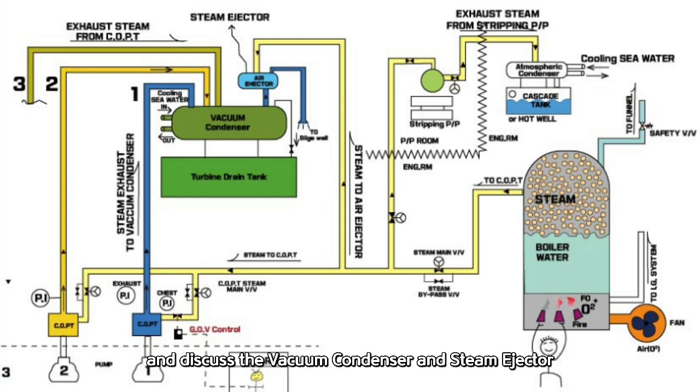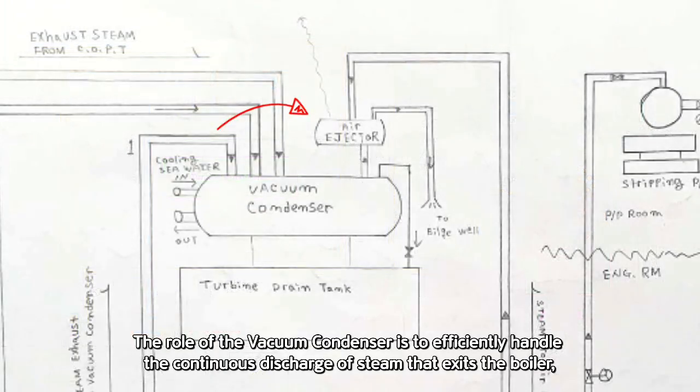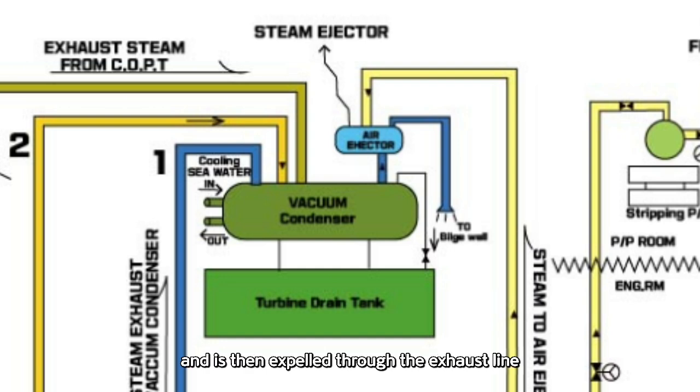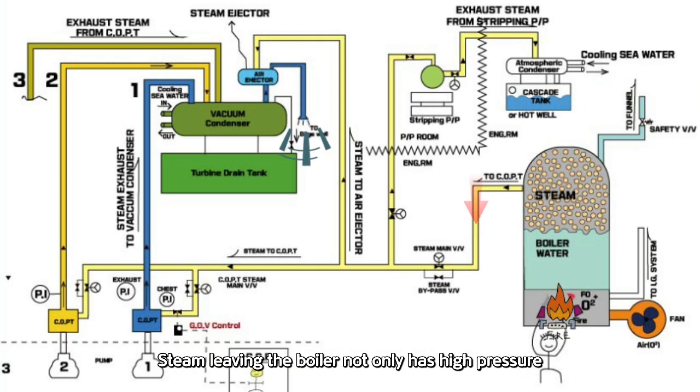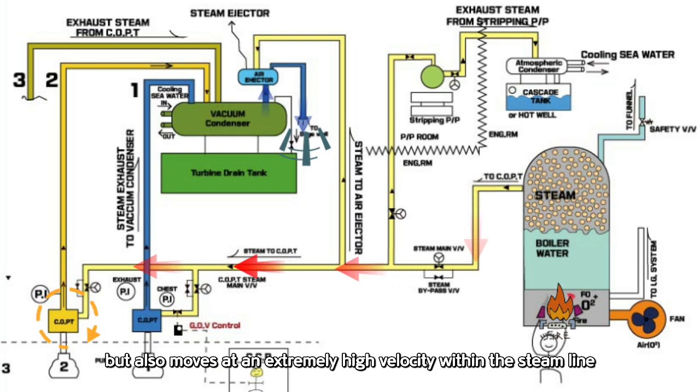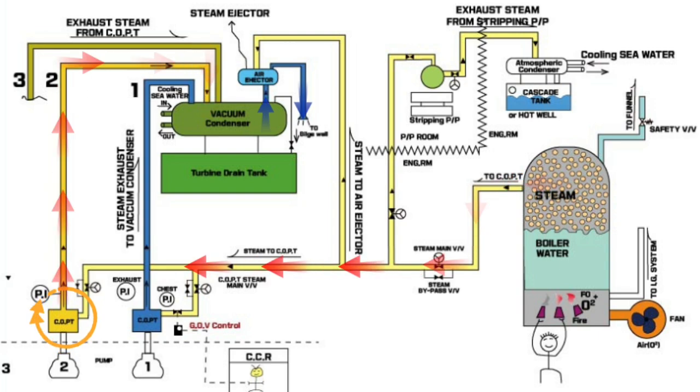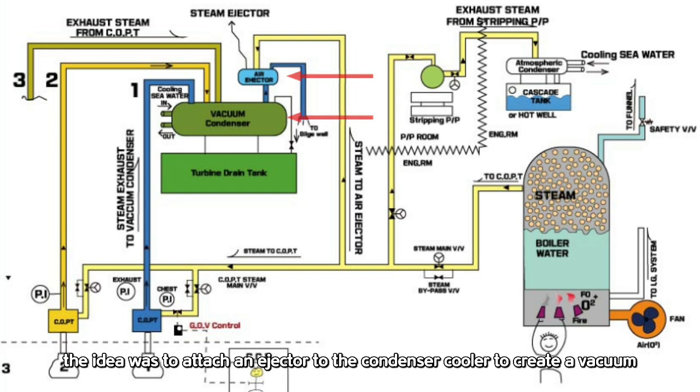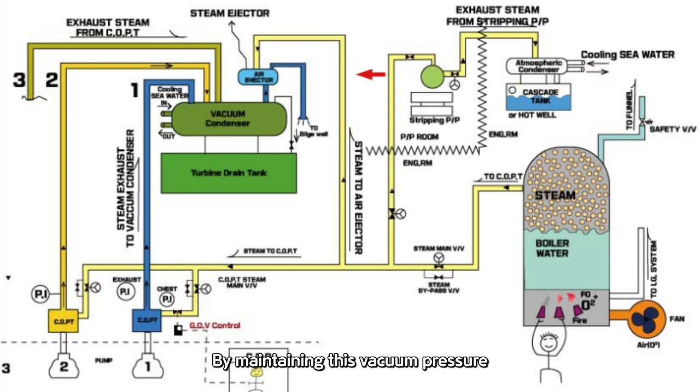Let's get back to the main topic and discuss the vacuum condenser and steam ejector. The role of the vacuum condenser is to efficiently handle the continuous discharge of steam that exits the boiler, circulates through the COPT, and is then expelled through the exhaust line. Steam leaving the boiler not only has high pressure, but also moves at an extremely high velocity within the steam line. To handle this, the idea was to attach an ejector to the condenser cooler to create a vacuum. By maintaining this vacuum pressure, it was expected to improve efficiency. This led to the development and installation of the vacuum condenser.